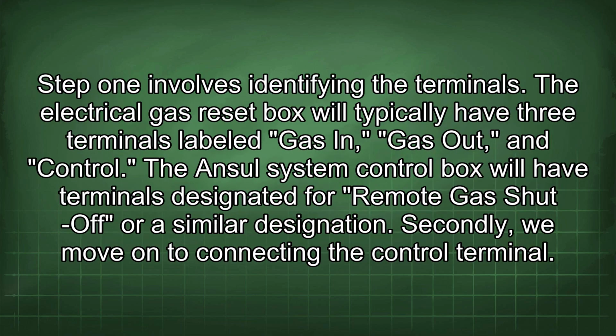Step 1 involves identifying the terminals. The electrical gas reset box will typically have 3 terminals labeled gas in, gas out, and control. The Ansul system control box will have terminals designated for remote gas shut off or a similar designation.